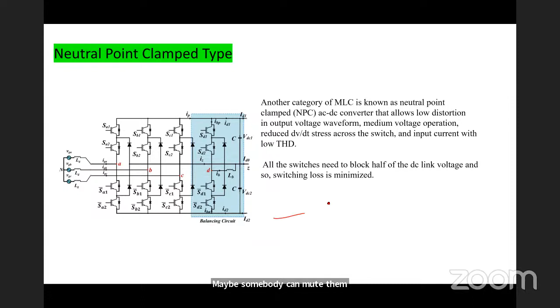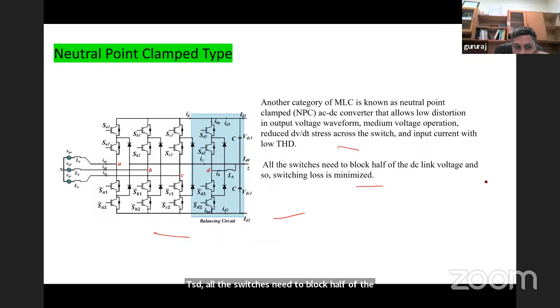So neutral point clamp type, another category of multi-level converter, known as NPC type, is very commonly seen. Its advantages are low distortion in the output voltage waveform, medium voltage operation, reduced dV/dt stress across the switch, and input current with low THD. All switches need to block half of the DC link voltage, so switching loss is minimized.